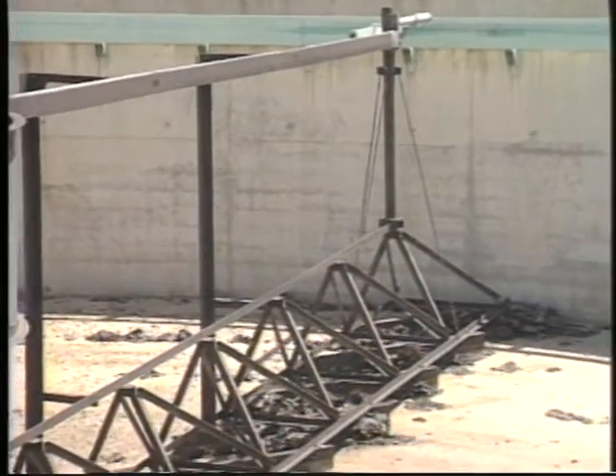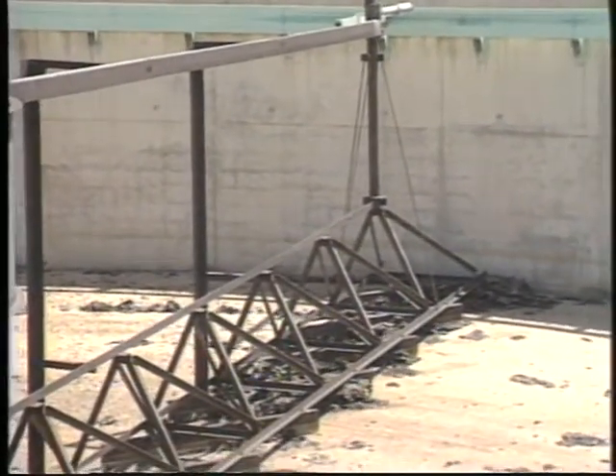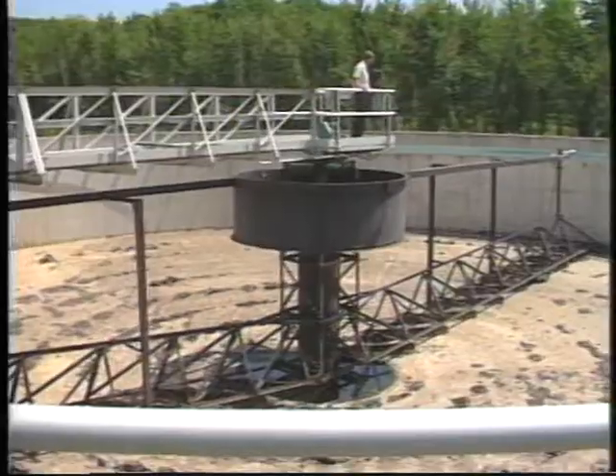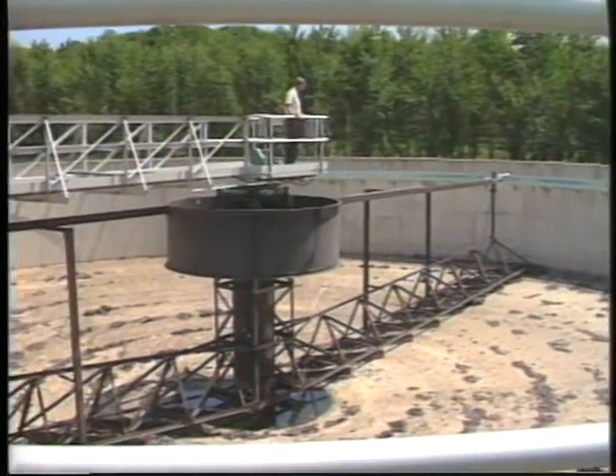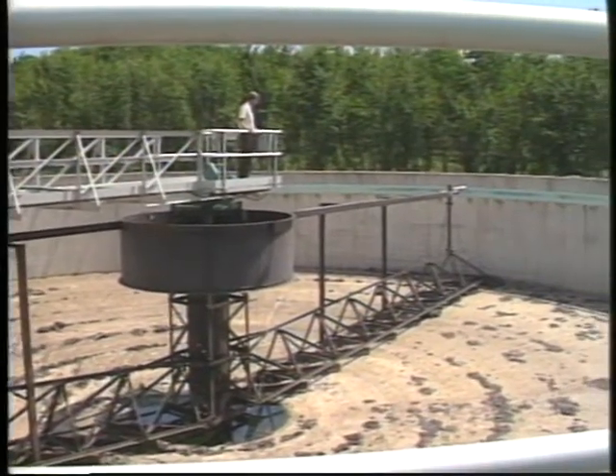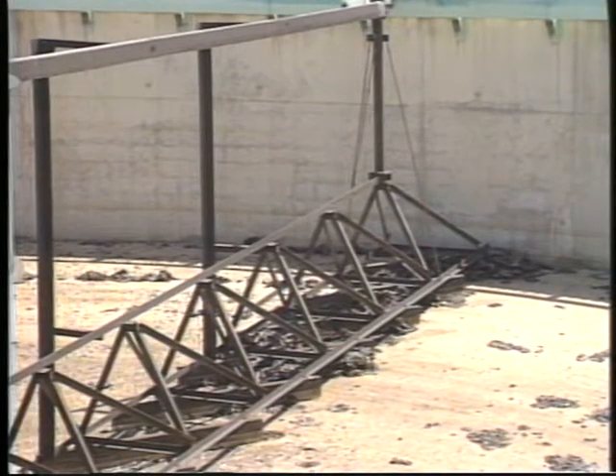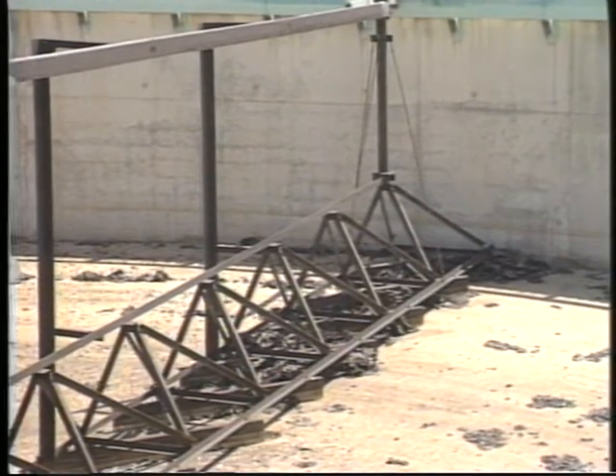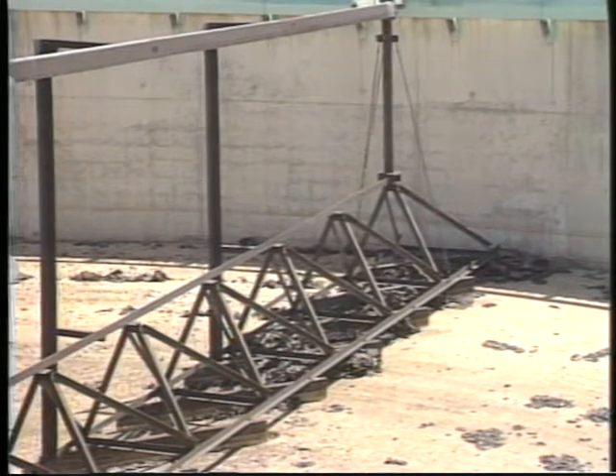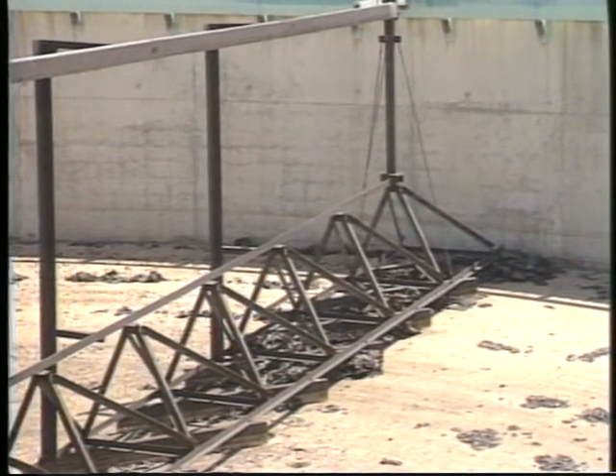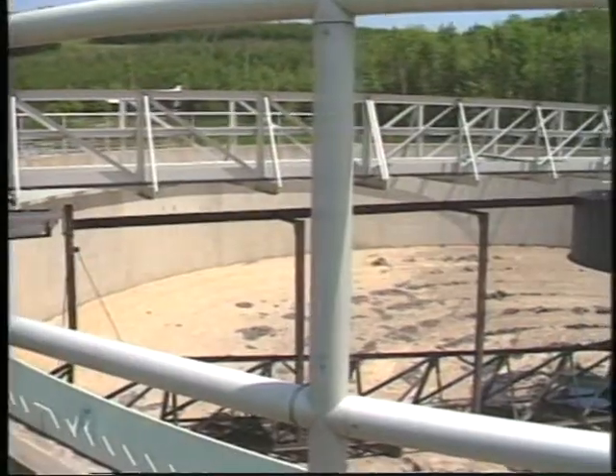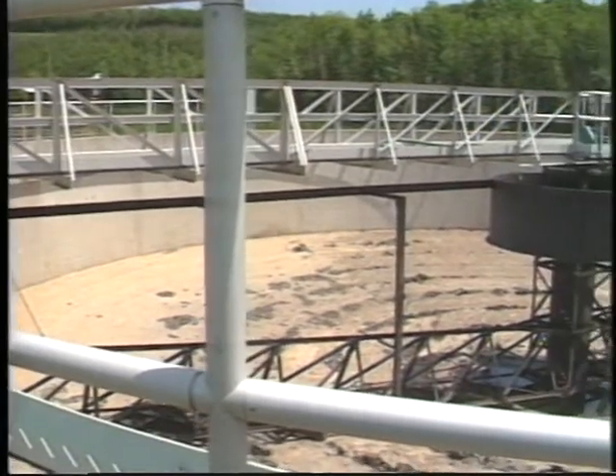The floor of the clarifier is usually sloped towards the center of the clarifier. The unit should be inspected for missing or maladjusted scrapers. The circular clarifier unit usually has a scum collection mechanism as well. Circular clarifiers have an overtorque device that will disengage the unit in the event of a jam or overload.